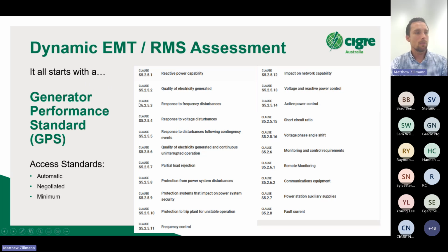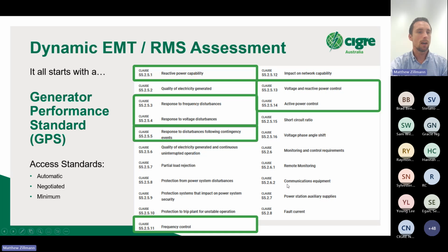As I said before, this all starts with performance standards. There are different levels, different performance requirements shown here on the right. If you ever want to have a look, check out the NER and Schedule 525. 525 sets out a whole heap of different technical requirements for generators, right through from what monitoring and control capability you have to have online, through to what reactive power you have to be capable of, what frequency and voltage disturbances you have to withstand, and how you should perform in different scenarios. Each one will usually have an automatic and a minimum access standard. The negotiated standard is, by definition, negotiated, so it's not defined, but it's usually somewhere between these two. In very rare occasions, you can see a negotiated access standard that's more onerous than an automatic access standard.